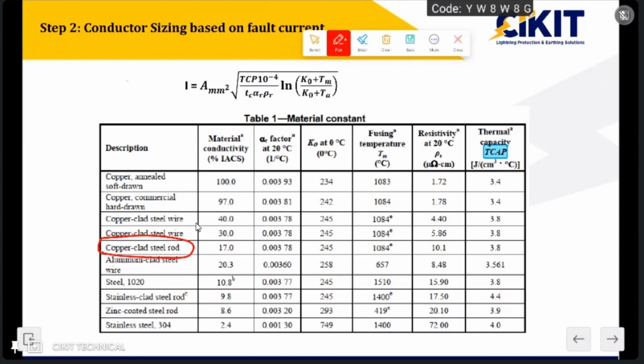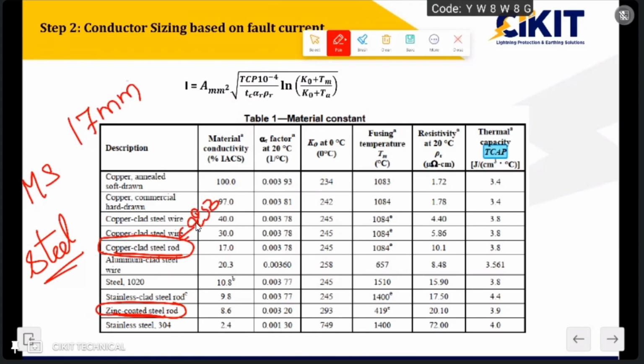Another material which we have been using for a longer period is the zinc coated steel rod. In both applications, copper coated steel and zinc coated steel, the core material is the same. We use steel as the core material, and in both cases we generally use MS material as the steel for the core. If we have copper coated steel or zinc coated steel with the same diameter of 17 mm, for copper coated we maintain a 250 micron coating, whereas for zinc coated we maintain an 80 to 100 micron coating. But the rod diameter is the same. Even though the rod diameter is the same, the current carrying capacity of copper coated steel won't be the same as that of the zinc coated steel rod. The difference is mainly because of this coating, in terms of microns: it is 250 microns, while this is only 100 microns.